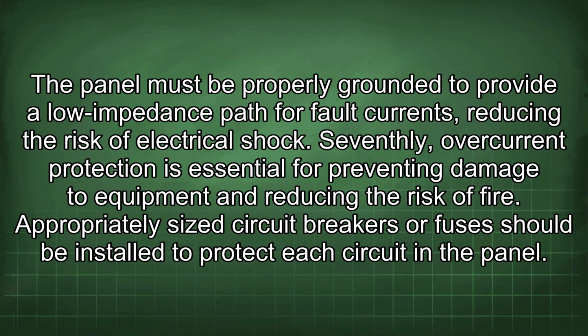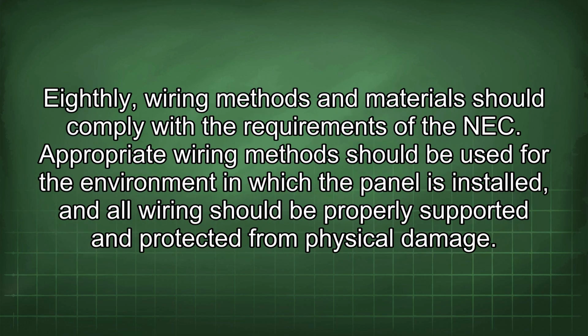Appropriately sized circuit breakers or fuses should be installed to protect each circuit in the panel. Eighthly, wiring methods and materials should comply with the requirements of the NEC. Appropriate wiring methods should be used for the environment in which the panel is installed, and all wiring should be properly supported and protected from physical damage.